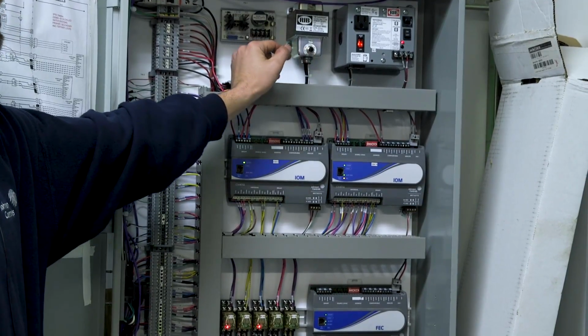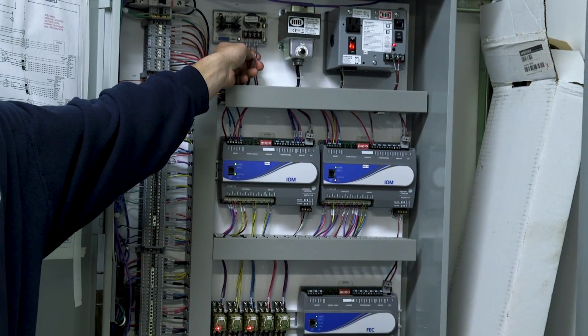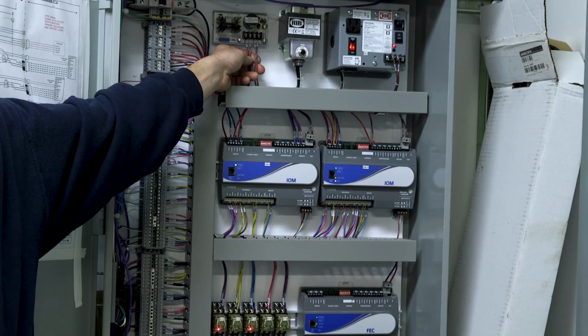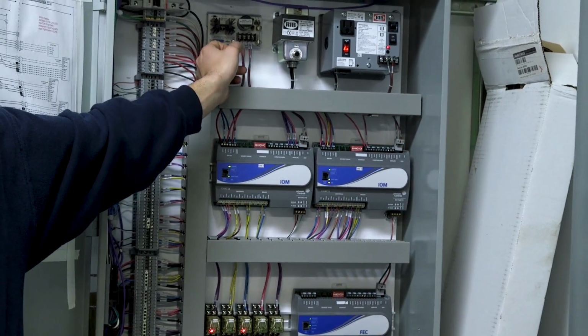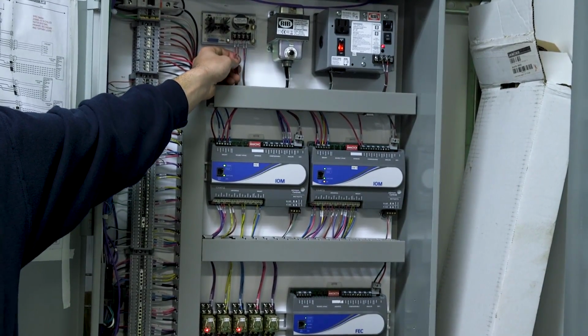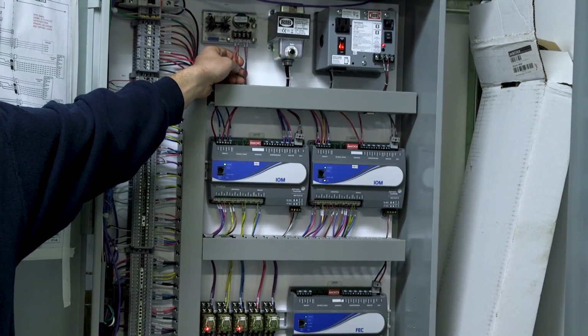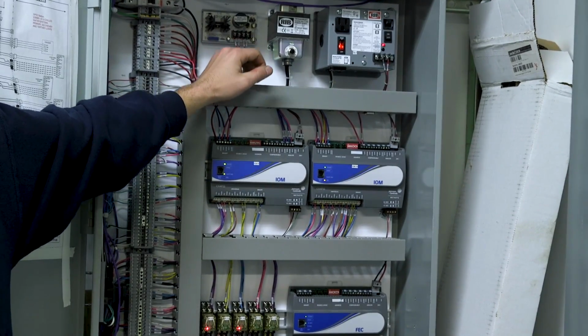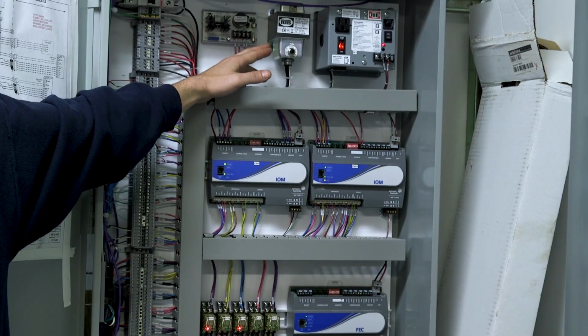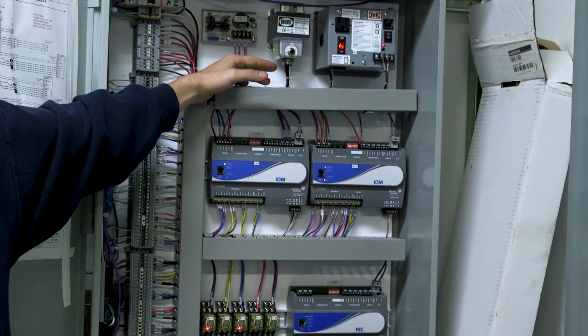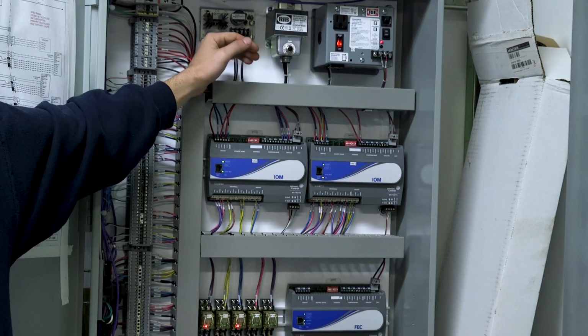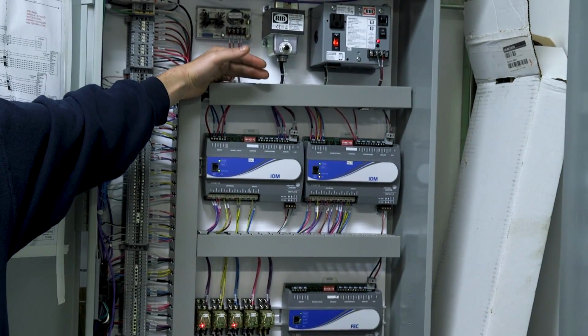This is your rectifier. This is what we're using for our DC power. So anything with a 4 to 20 milliamp signal will be coming off of this. So if for any reason any of your temperature sensors or anything like that go out, you want to check to make sure that this is good or this fuse isn't blown. Because a lot of times when you see multiple temperature sensors go out, it's because your rectifier went bad or a fuse blown.